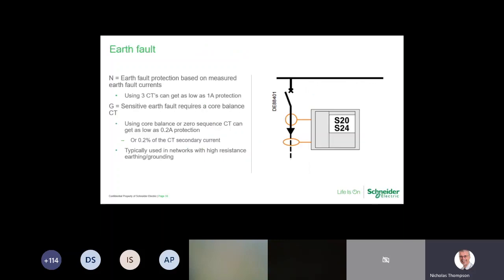Now, earth fault, N and G. So earth fault uses the standard 3 CT method. You can get down as low as 1 amp. So I think for normal everyday applications, that's probably going to be acceptable. Where you get problems with earthing, or sometimes people refer to them as hot sites, is where the earth path back to the primary transformer is very bad.